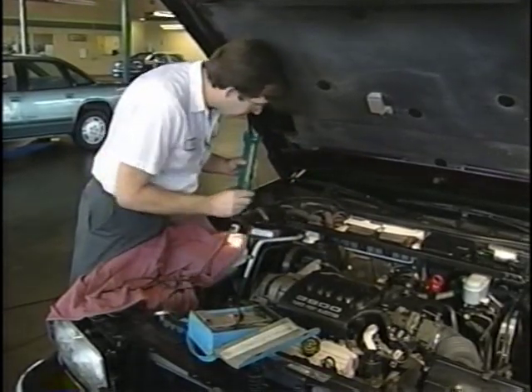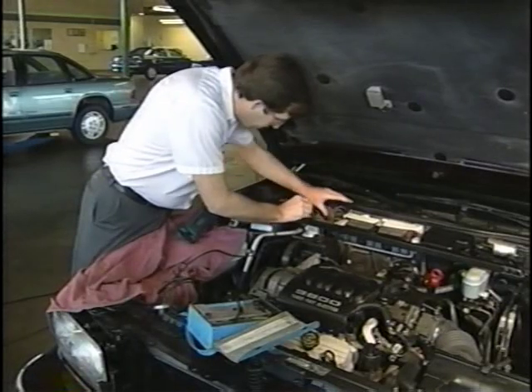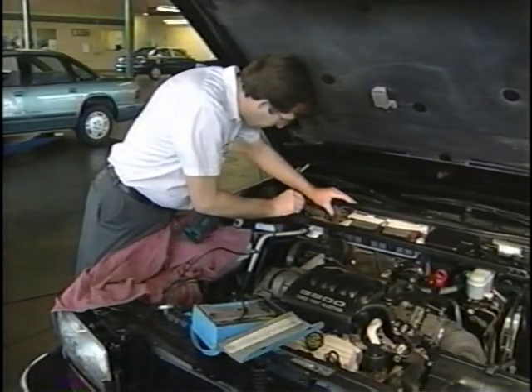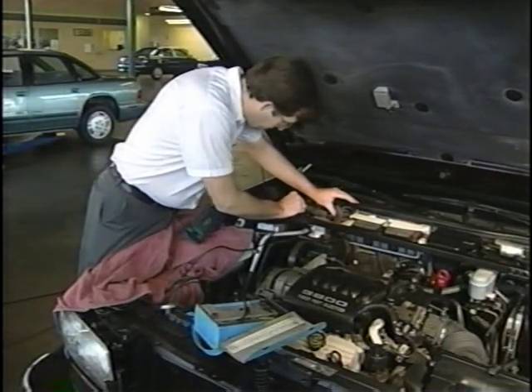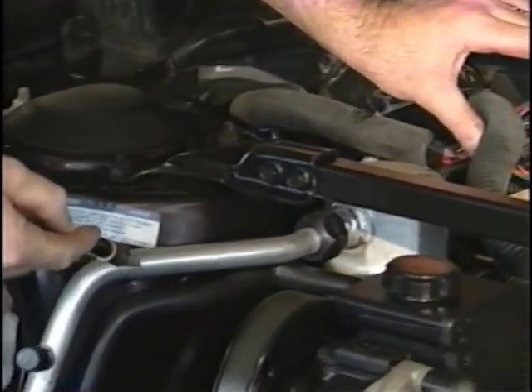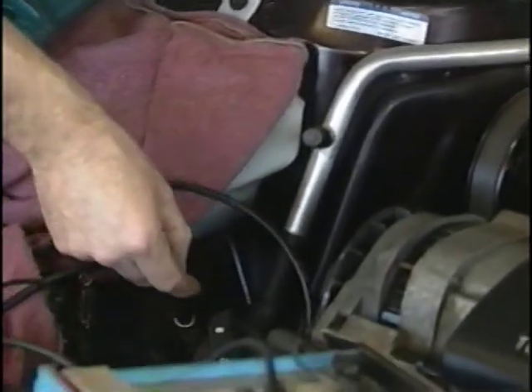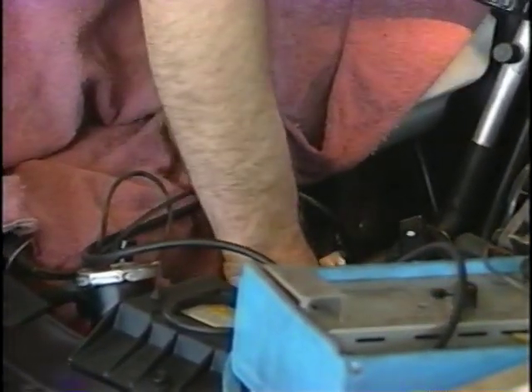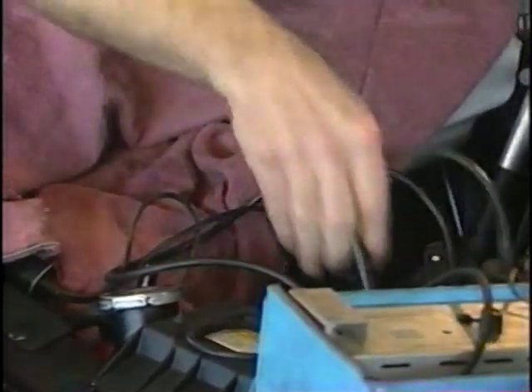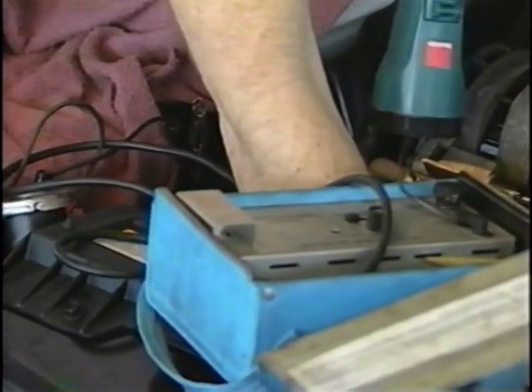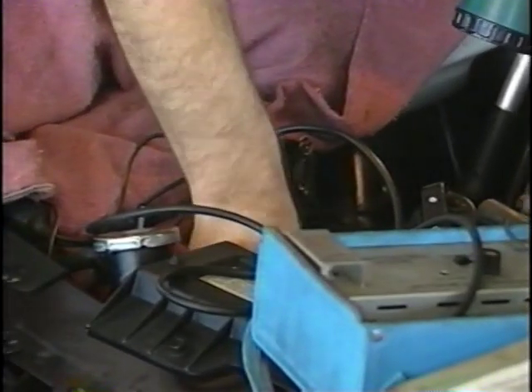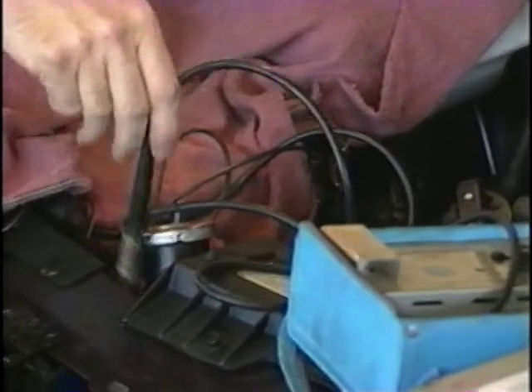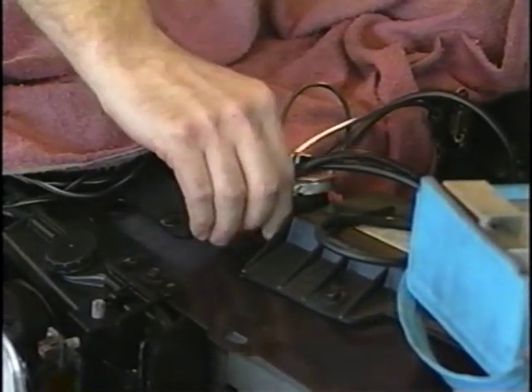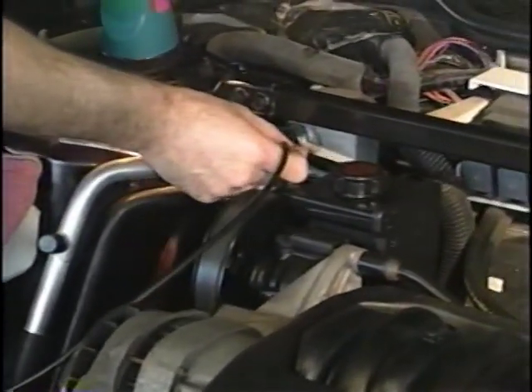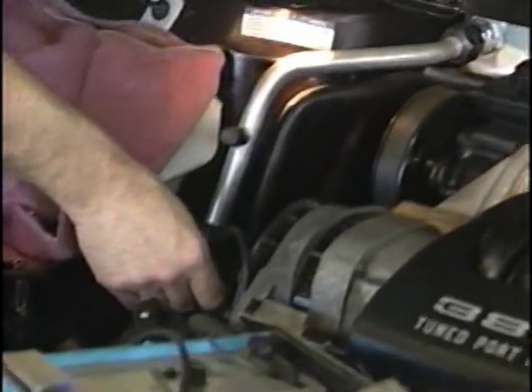Okay, and then you want to take the leak detector and go around all the fittings or any possible place you might have a leak or suspect you have a leak. Around the switches. Just follow the system all the way from one end to the other. Follow down all the lines. Down to the compressor. Another switch down there. Follow the line back up to the condenser. Down the side of the condenser and the pipes. Back up the other line. Back to the core. Check all, especially the fittings and anywhere the line you can get to.